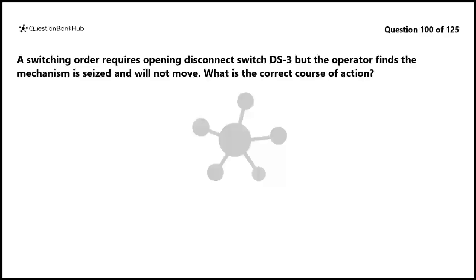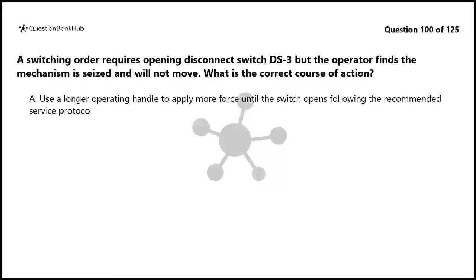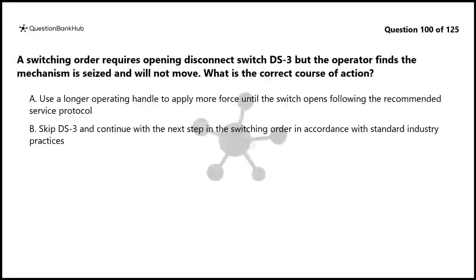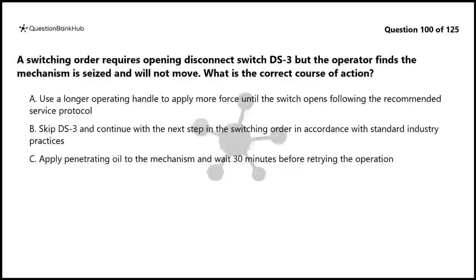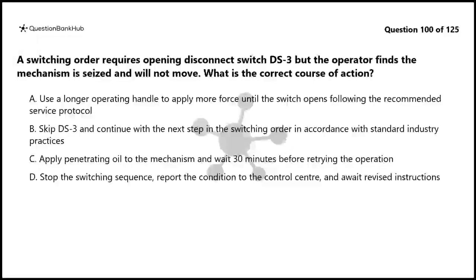Question 100. A switching order requires opening disconnect switch DS3 but the operator finds the mechanism is seized and will not move. What is the correct course of action? A. Use a longer operating handle to apply more force until the switch opens following the recommended service protocol. B. Skip DS3 and continue with the next step in the switching order in accordance with standard industry practices. C. Apply penetrating oil to the mechanism and wait 30 minutes before retrying the operation. D. Stop the switching sequence, report the condition to the control center, and await revised instructions.